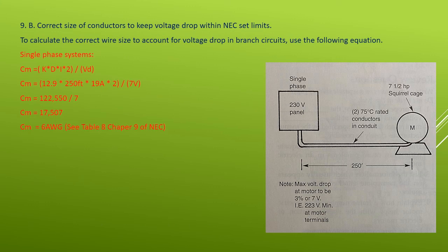Here we have substituted each of the variables with its appropriate value. For the DC constant, we have 12.9, which is the constant for copper. We have a one-way distance of 250 feet. You multiply that also by your full load current, which is 19 amps, and by 2 for a single phase system, which is this system here. We multiply all those, we get 122,550, and we divide by 7 volts, we get 17,507.